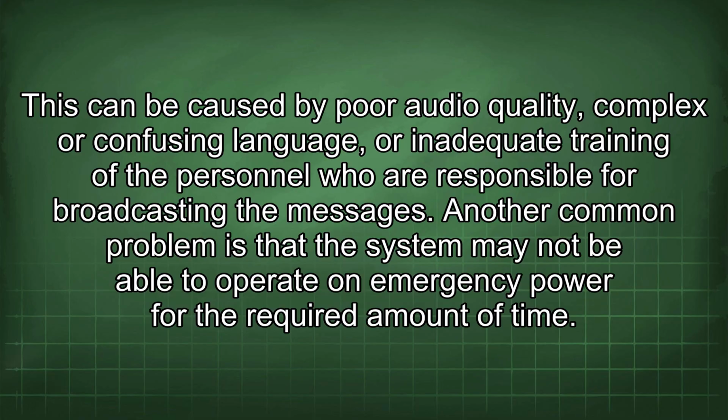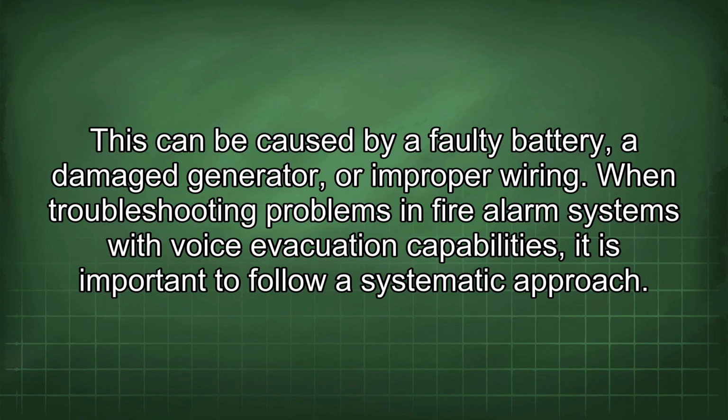Another common problem is that the system may not be able to operate on emergency power for the required amount of time. This can be caused by a faulty battery, a damaged generator, or improper wiring.